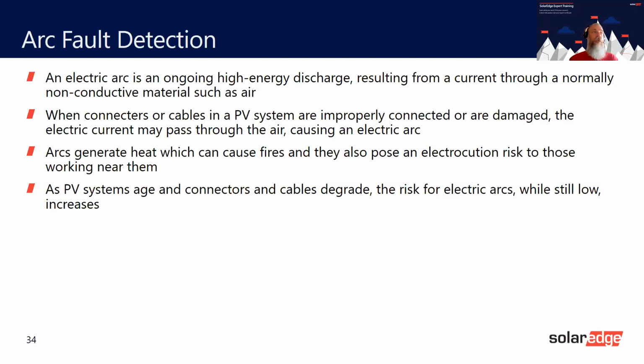And once we know that there's an arc, it then turns off, and then the safe DC comes in automatically, and basically that lowers the voltage down to 50 volts or 25 volts, and the current down to 300 milliamps. Okay, so very, very safe.